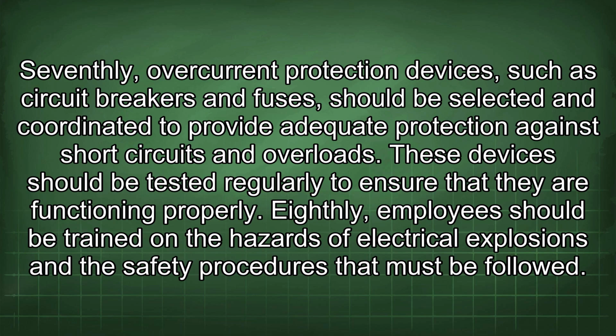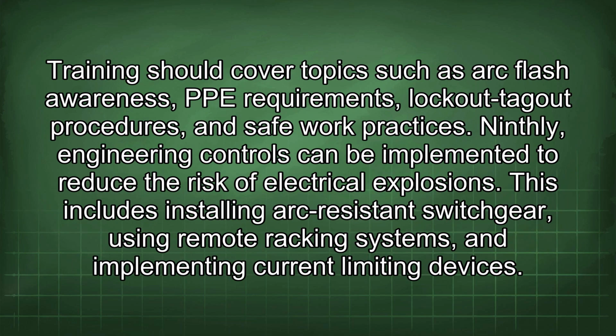Seventhly, overcurrent protection devices, such as circuit breakers and fuses, should be selected and coordinated to provide adequate protection against short circuits and overloads. These devices should be tested regularly to ensure that they are functioning properly. Eighthly, employees should be trained on the hazards of electrical explosions and the safety procedures that must be followed. Training should cover topics such as arc flash awareness, PPE requirements, lockout-tagout procedures, and safe work practices.